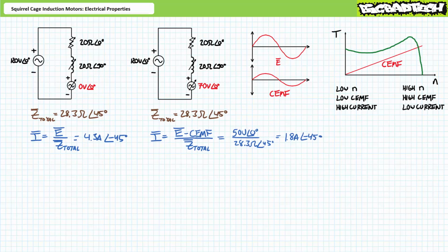Like I said, we'll examine inrush in greater detail in later lectures. More to the point of this lecture is that every component inside this model changes at different points of the speed-torque curve. Given specified supply voltage magnitude, counter-electromotive force magnitude, and impedance values, it should be well within your capacity to calculate current and power. Allow me to demonstrate.